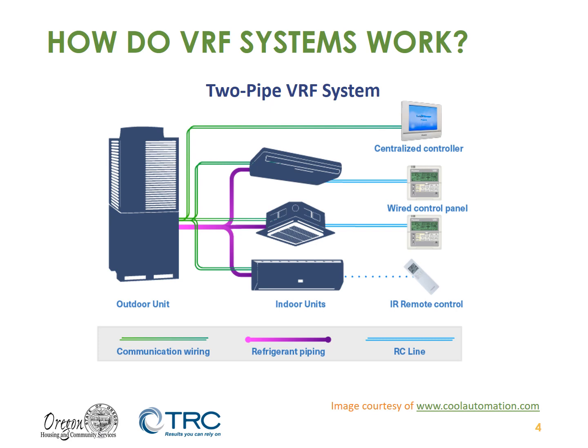These systems, however, can also be controlled by a centralized controller, which makes them a little different than a lot of other multi-split systems. And this may be much more common in a commercial application where you'd like to have a central controller truly determining the temperatures and air movement in each of the different zones being addressed. So this is our traditional two-pipe system. It works very well, very highly efficient, but it works very similar to a multi-split system, just with a lot fewer refrigeration lines running. In this scenario, the indoor units can be either heating or cooling in most cases.